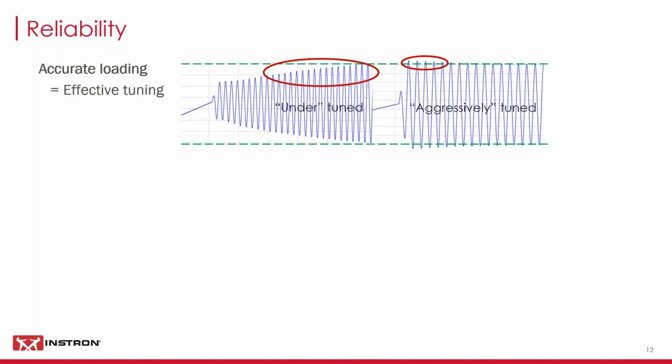If we look at accurate loading, aside from obviously aspects of calibration and load cell accuracy, when you look at a dynamic test, it's important that you tune your control system. I'm not going to talk about this at length today. One of my colleagues did a really nice webinar a few weeks back, which you'll be able to replay. If you look at the Instron website, you will find a page of webinars, and all the ones we've recorded during this year can be replayed at your leisure. I would genuinely recommend, if you don't know much about dynamic systems, so fatigue test systems, that you go and watch that one about tuning, because it's a really important effect.